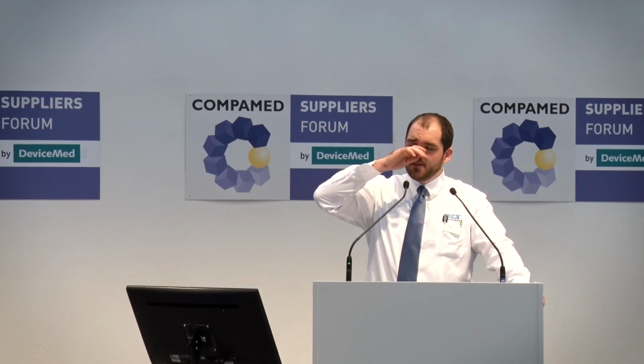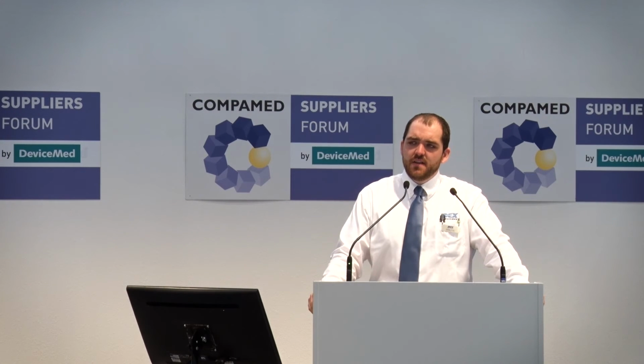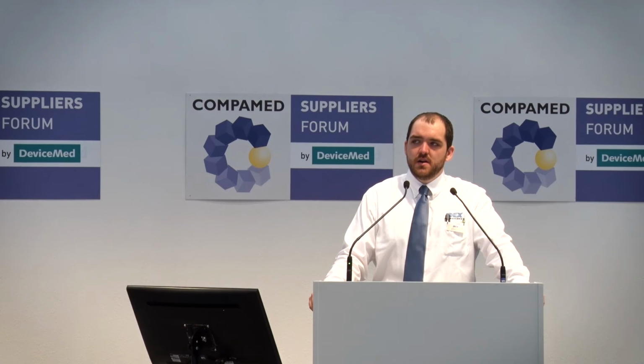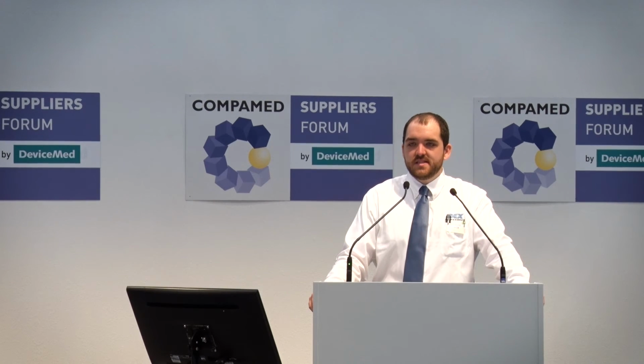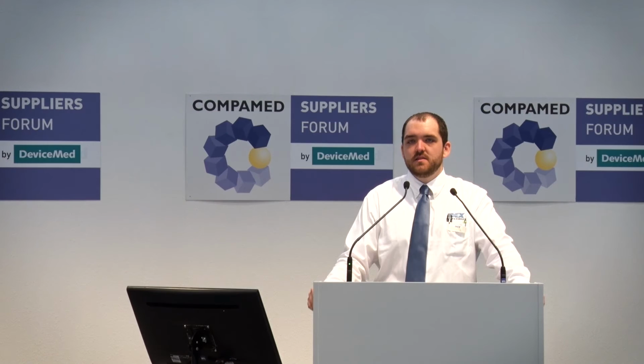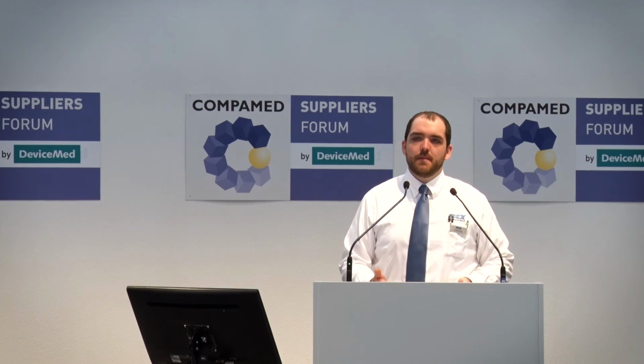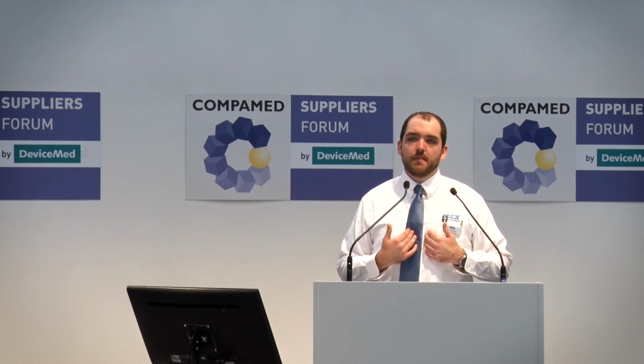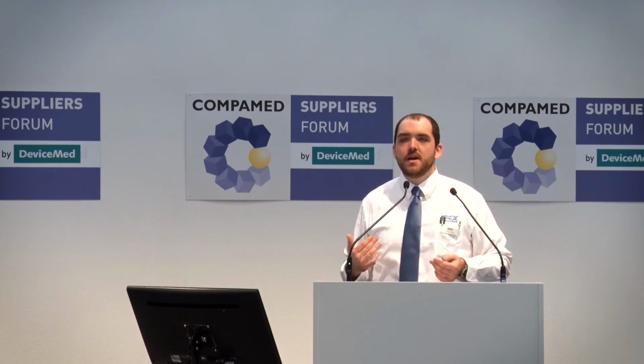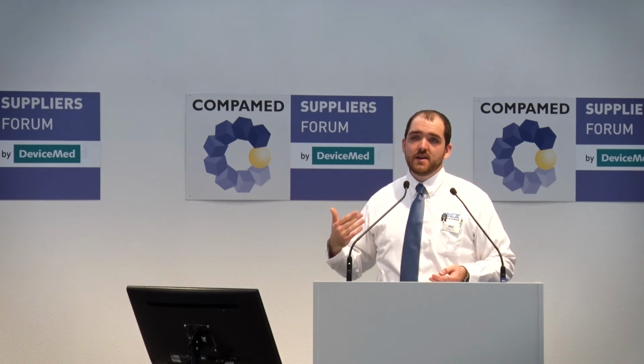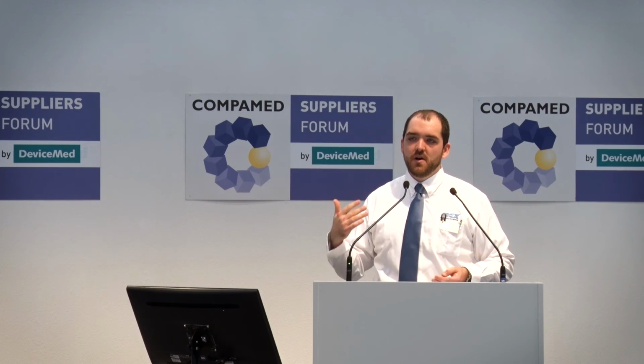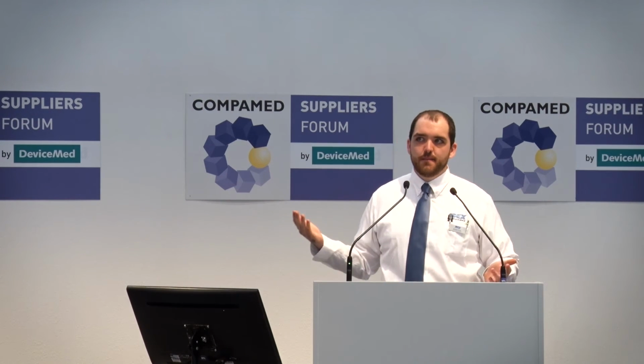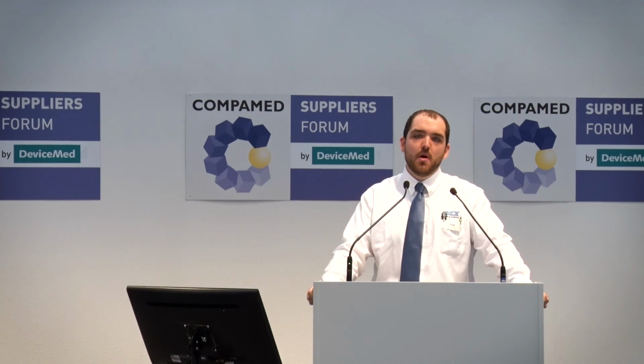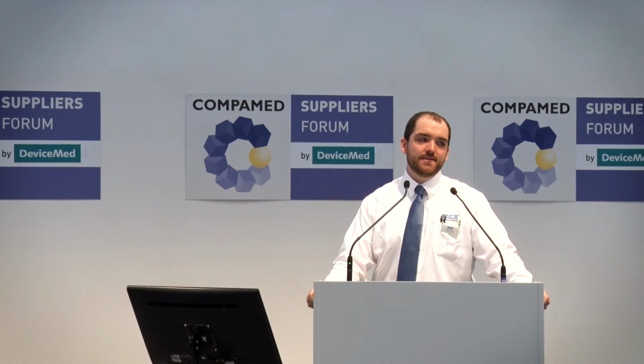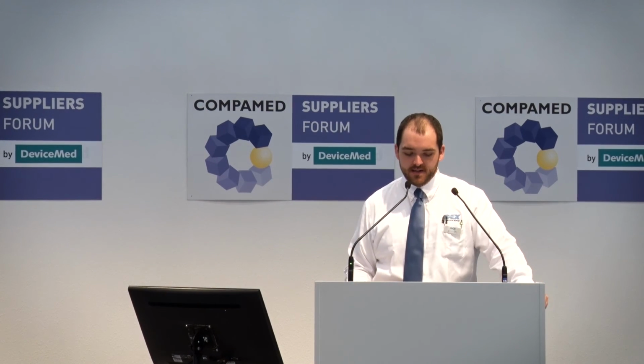Another one, we've heard this a couple times as well, is another customer looking to monitor the flow rates on the waste side of things. What the waste side allows you to do is you don't have to worry about our sensor coming in contact with your reagents before you use them. Instead, you're just monitoring the waste and making sure that you're getting a consistent amount of flow that you're looking for. It's good for a peristaltic pump draw system. You'll be able to monitor the flow rate and make sure that your peristaltic pump is working the way you want it to work.